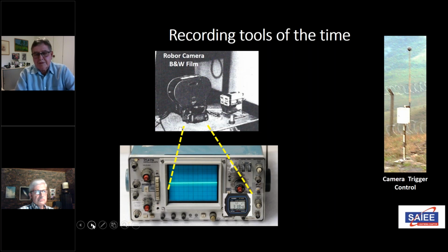One of the first industrial contract projects I took on was with the South African Railways, who were being disturbed by high voltage surges in the overhead catenary system, damaging equipment on the trains. They didn't know whether it was lightning, switching surges, or some other problem. Since my role had been to build up high voltage work, we developed high voltage potential dividers to measure overvoltage surges and installed those on the railway line. We then needed a way to automatically capture whatever surges occurred on the oscilloscope, so we used these robot cameras in a horizontal mode to automatically capture surges. This oscilloscope shown is much more modern than the ones we started with back then, which is now almost 50 years ago.